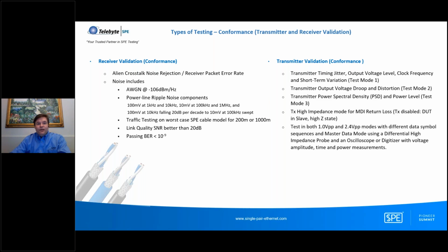Then with power over data line, we also may have power line ripple noise. So we're adding low frequency ripple noise from 1 kilohertz to 1 megahertz, and that basically simulates an environment that you might see on the single pair cable. Then we're using different cable lengths. We could test over 200 meters for a spur, or we could test long cable lengths up to 1,000 meters or beyond, actually, for trunk connections. And we're looking to keep the SNR, even with this noise condition, better than 20 dB. We want to make sure that our bit error rate is very low so that we get error-free traffic. So we're going to pass Ethernet or even upper layer traffic, layer 3 IP traffic, or layer 4 with the TCP or UDP protocols when we test this.